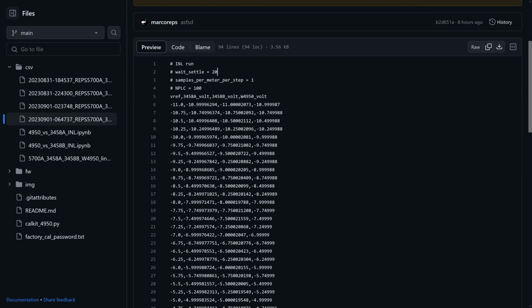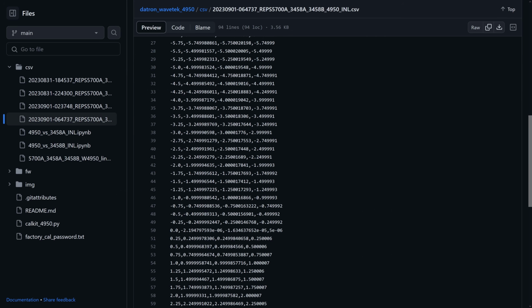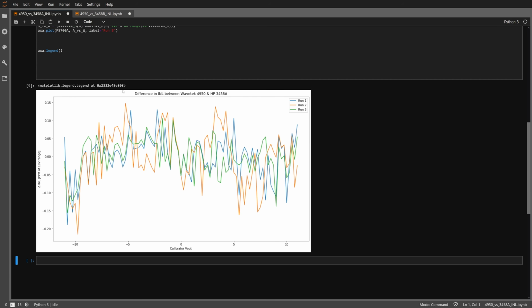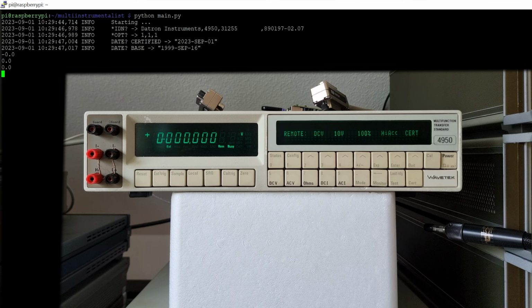This was a bit of a shocker, I must admit. It is amazingly good, much better than what I would expect from a 7.5-digit class device. I wonder if Datron 1271, which uses a similar looking ADC, is as good as this. I'm publishing the data on GitHub, link below. Similar story in the noise department. It is basically noise-free down to the least significant digit on the 10 volt range.